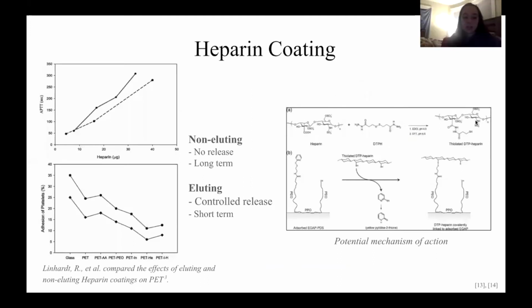So on the left, you can see we considered two ways to incorporate a heparin coating onto the leaflet surfaces, either as an eluting or non-eluting coating. One study compared ionically and covalently bonded heparin coatings on a PET polymer. While the results showed a higher activated partial thromboplastin time for the ionic coating, researchers found increased bioactivity and reduced platelet adsorption in the covalently immobilized coating compared to the ionic coating.